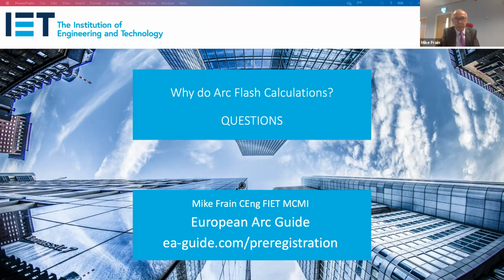The other thing is I remember seeing a situation where somebody got burnt on the hands. They were doing something silly, plugging a circuit breaker onto a high specification board, but it flashed over in the hand. If I'd done the incident energy calculations, it's likely there would have been very little incident energy at his body, but much higher at his hand, causing a burn to his hand and forearm. He went to hospital, they cleaned it, dressed it, and sent him home again.